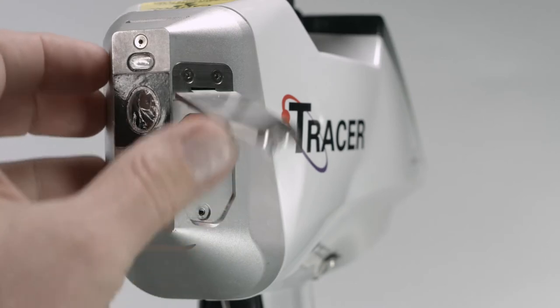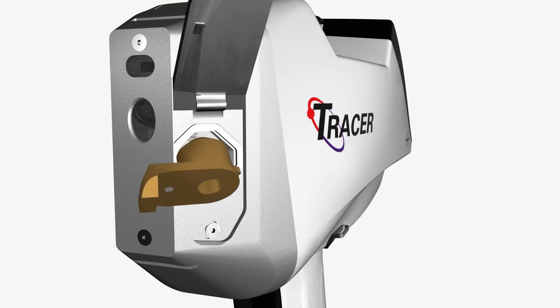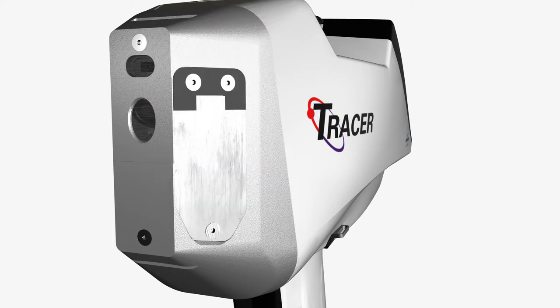The Tracer 5i not only incorporates an automated internal filter wheel, it also has a manual filter insertion slot for user-created filters or secondary targets, to help study non-standard materials or to fine-tune analyses of particular elements of interest.